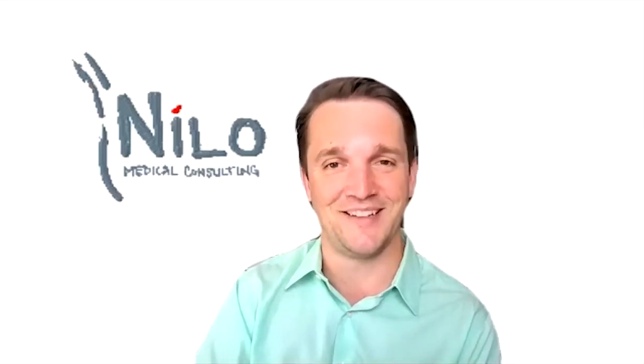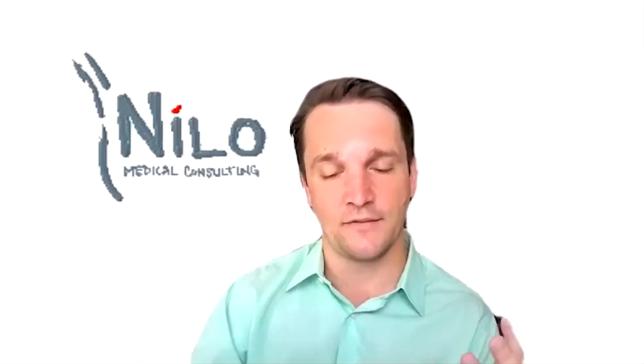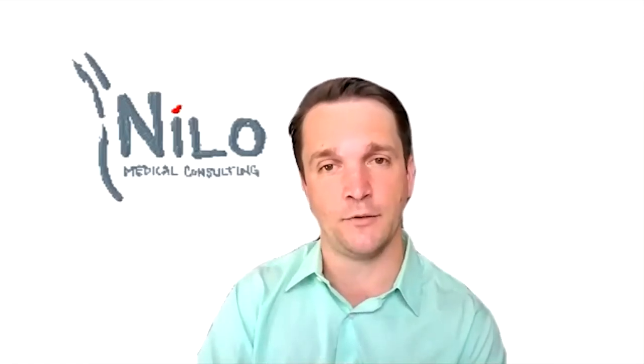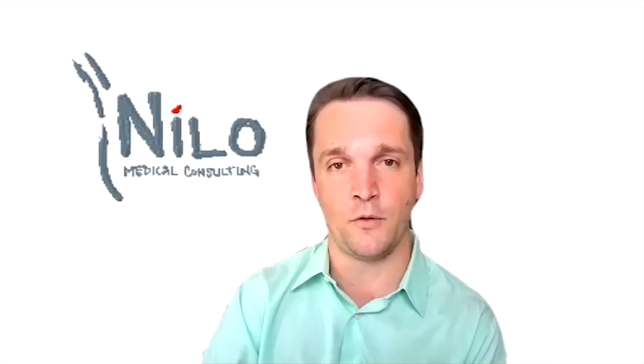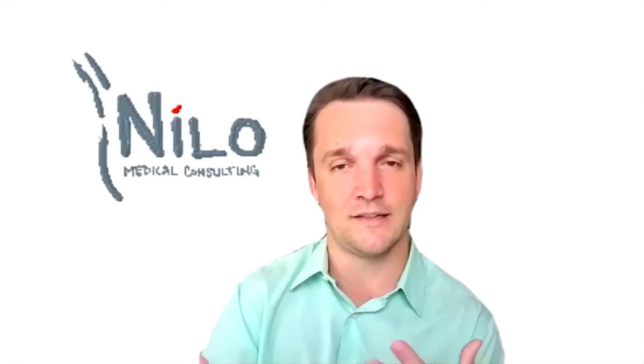Unless there are interactive questions, after a certain amount of time you'll likely start to hear from the FDA, and it'll be questions. This is after the review team has come back together with their reviews. They'll be asking questions about: can you define your user and your device better? How did you run this test? We have questions about this validation effort. We didn't see cybersecurity in your submission. Where is that testing?